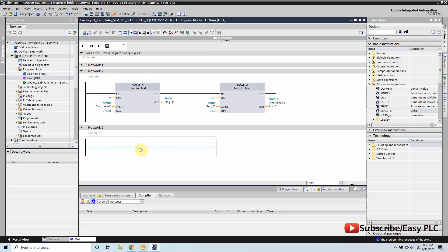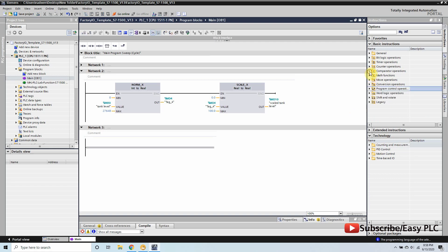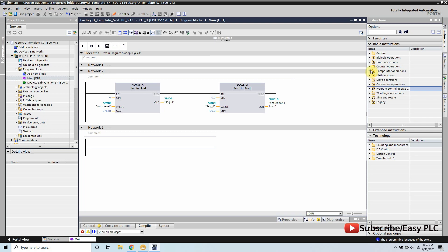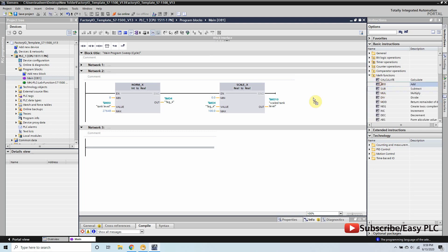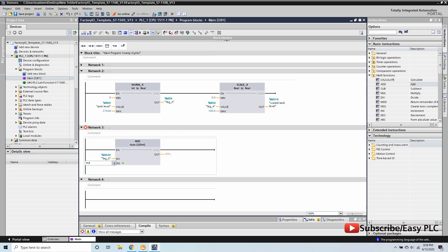In Network 3 we will make the logic for the level high status. To control the tank level smoothly, we have to open the filling valve when the water level is less than the setpoint and close the filling valve when the tank level is a few points higher than the setpoint. For example, we will start tank filling at 50 liters and stop filling at 52 liters, so we have a window of 2 liters to start and stop the water actuator valve. Otherwise the system will become unstable.